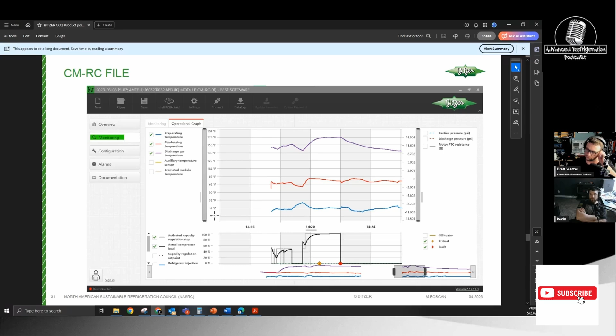But I see what you're saying, where you could potentially just have the pressure switch in there. But here's the thing: when people go in there to do a controls conversion, they're going to do it exactly the way it is, right? They're not going to spend the extra 4 hours it might take to rewire in the low pressure switch. Oh no, I'm not wiring them back in. No, but if someone would decide to do that, instead of doing the whole switchback thing, get rid of it, and then just wire that low pressure switch, reroute it where it would have been.